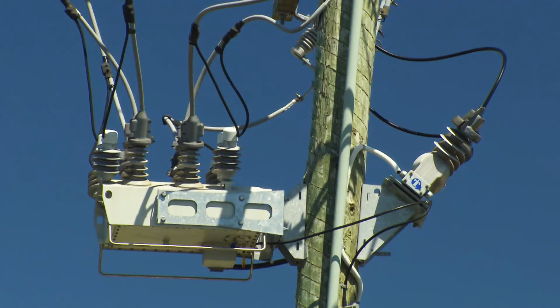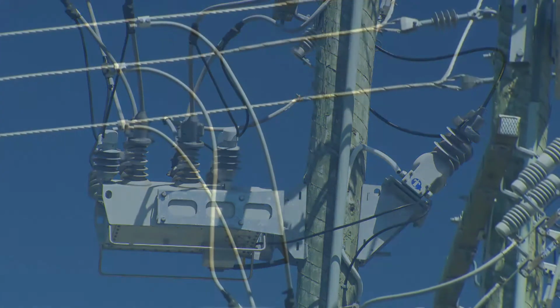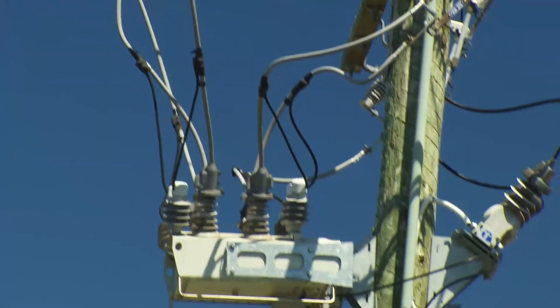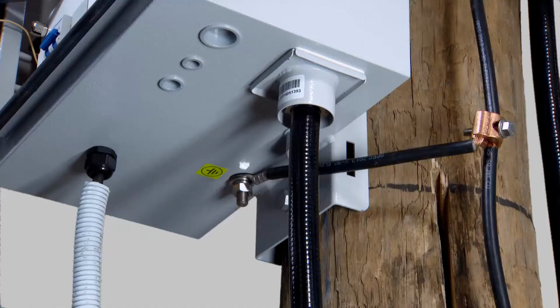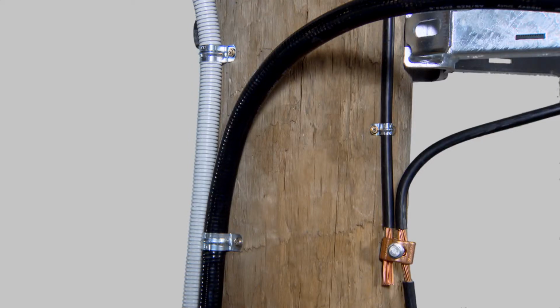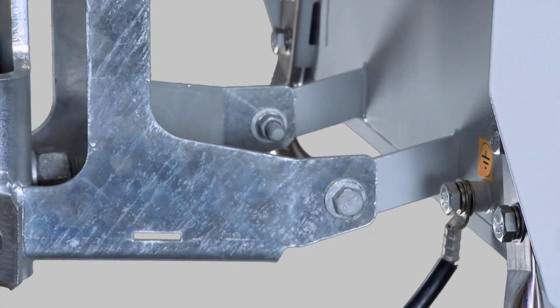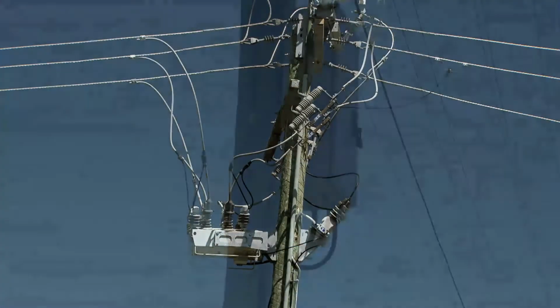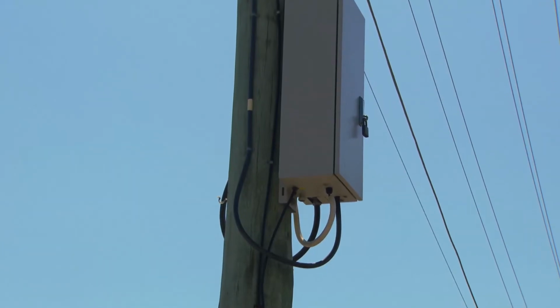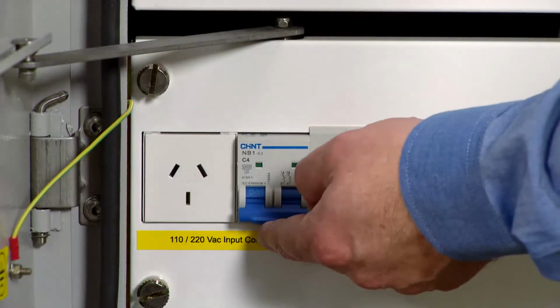The installation should be checked before final commissioning. Check that all of the high voltage connections have been tightened. Inspect the earth wiring and confirm it's been connected as specified in the user manual. Inspect the low voltage wiring is complete and connected safely. Check the low voltage supply is on.